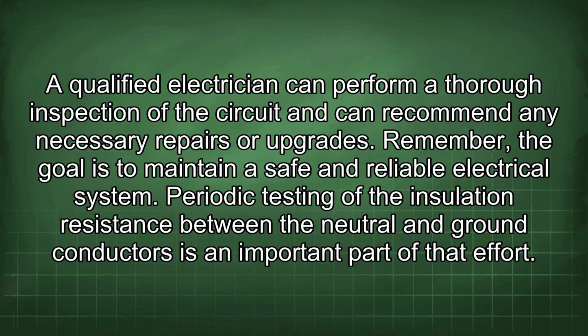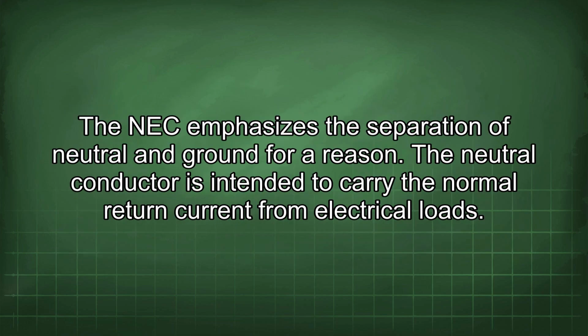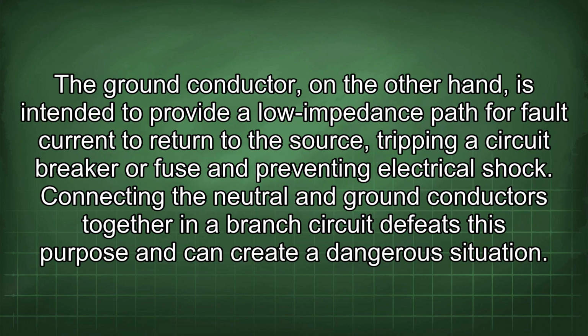Periodic testing of the insulation resistance between the neutral and ground conductors is an important part of that effort. The NEC emphasizes the separation of neutral and ground for a reason. The neutral conductor is intended to carry the normal return current from electrical loads. The ground conductor, on the other hand, is intended to provide a low impedance path for fault current to return to the source, tripping a circuit breaker or fuse and preventing electrical shock. Connecting the neutral and ground conductors together in a branch circuit defeats this purpose and can create a dangerous situation.